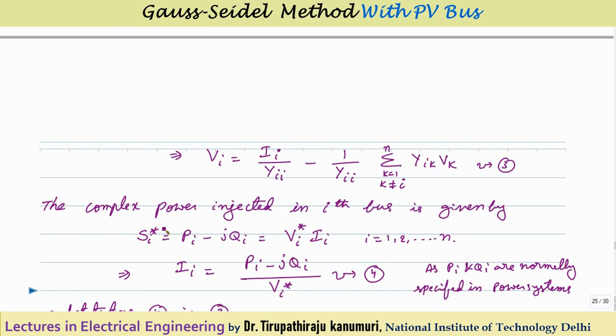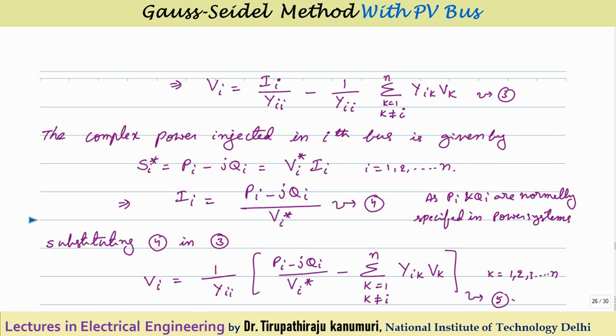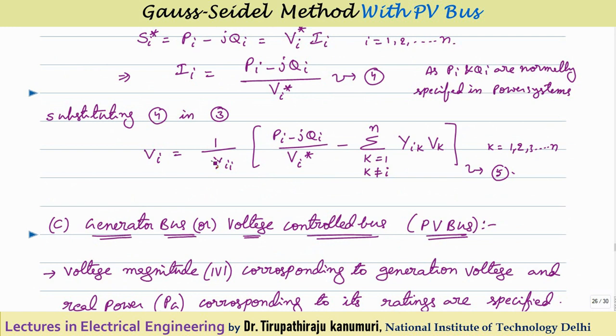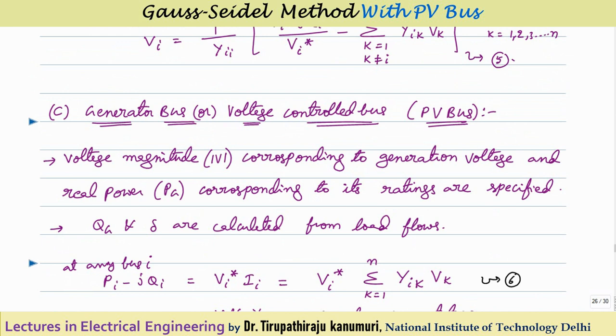Taking the conjugate, Si* = Pi − jQi = Vi*·Ii, so Ii = Si*/Vi* = (Pi − jQi)/Vi*. Since most buses are load buses where P and Q are known but I is unknown, we substitute this expression for Ii into the voltage equation. This gives Vi = (1/Yii)·[(Pi − jQi)/Vi* − Σ(k=1 to N, k≠i) Yik·Vk]. Notice that Vi appears on both sides, which is why iterative methods are needed.